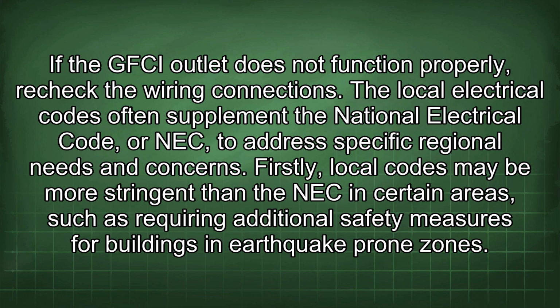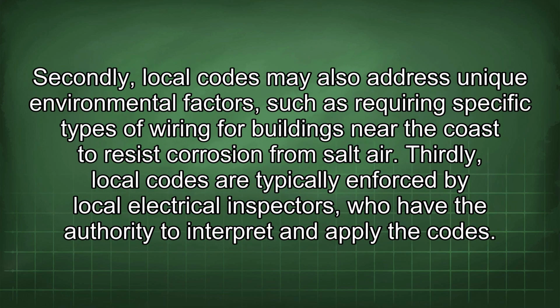The local electrical codes often supplement the National Electrical Code, or NEC, to address specific regional needs and concerns. Firstly, local codes may be more stringent than the NEC in certain areas, such as requiring additional safety measures for buildings in earthquake-prone zones. Secondly, local codes may also address unique environmental factors, such as requiring specific types of wiring for buildings near the coast to resist corrosion from salt air.